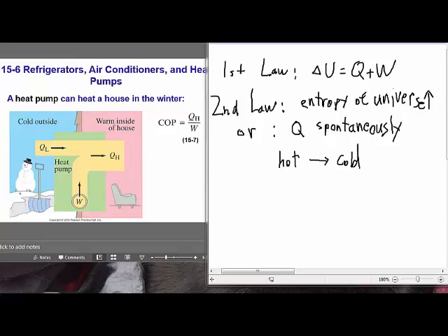So a heat pump doesn't break any law of thermodynamics when it's more than 100% efficient. It might have a coefficient of performance of maybe 3, but a propane heater, kerosene heater, a plug-in electric heater, none of these could go above 100% efficiency. And therefore no other type of heater could have a coefficient of performance greater than 1.